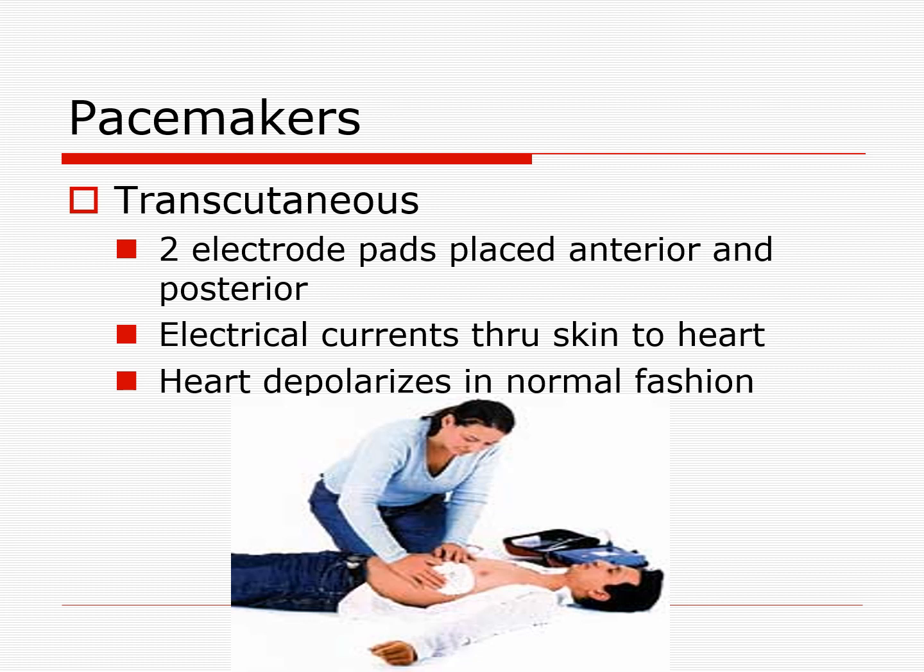They're pacing on a mannequin, showing you how they increase the voltage so they capture, then they back off one setting so they don't overshoot, while making sure they're maintaining a blood pressure.